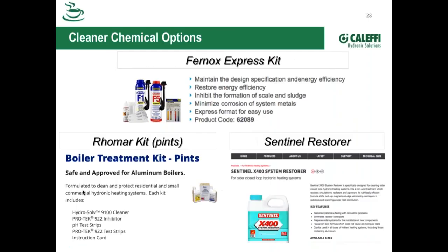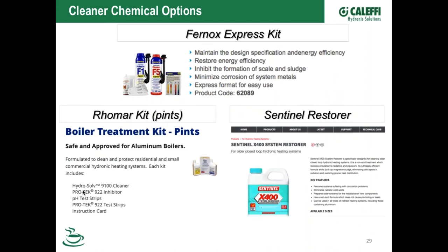Here's an example of some of the kits that are out there that make it easy for you to do these steps. Like the top one there, that Fernox - those are little aerosol cans with a hose bib connection, and you just screw them onto your boiler drain or some hose connection on your system. Some of our dirt kettles have a hose connection on the bottom that you could squirt this fluid into. So you put the cleaner in first, the first product, and run that for a day or so, then flush that out. They give you little pH test strips to make sure you've got it flushed out.